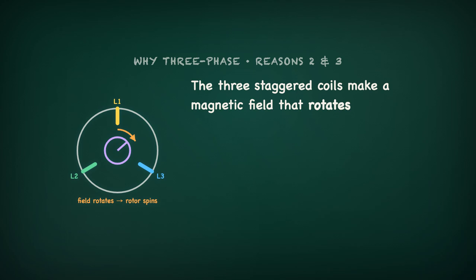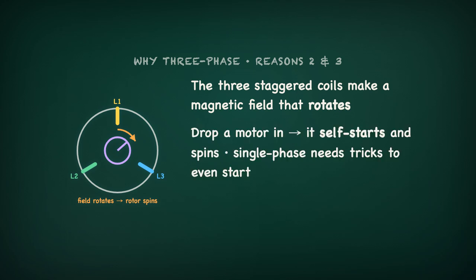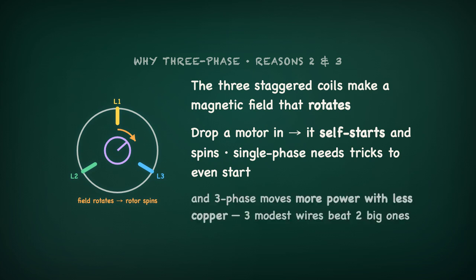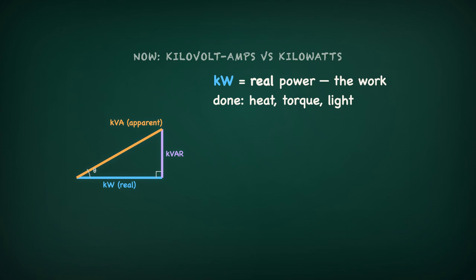That smoothness buys two huge things. First, those three staggered coils create a magnetic field that actually rotates. Drop a motor into that rotating field and it just spins, all on its own. A single phase motor needs extra tricks just to start turning. Second, three phase moves more power with less copper. Three modest wires beat two big ones. Cheaper to build and cheaper to run.